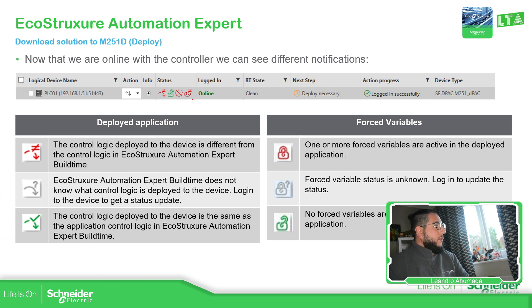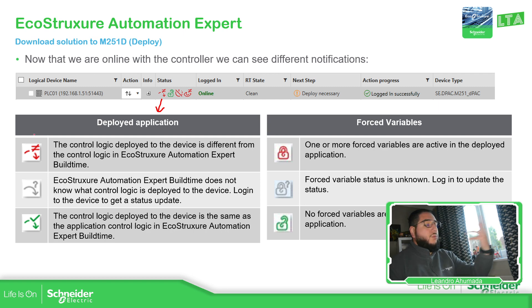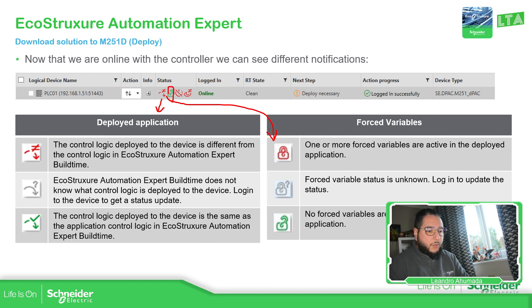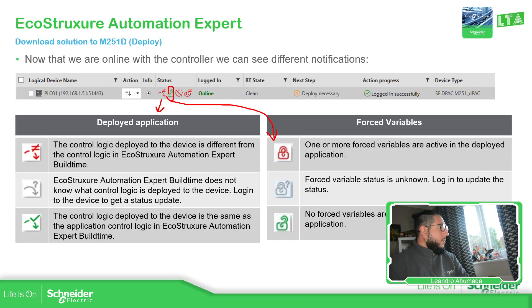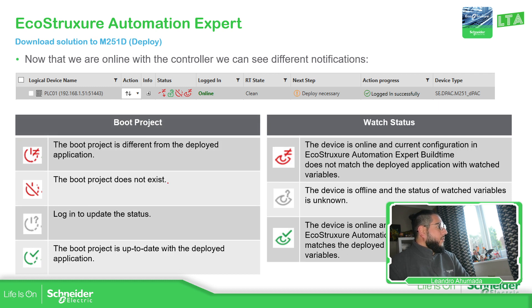As soon as you log in you have different things. This icon over here is about the application — basically it means the application you have on the software is different from what's on the controller. That's why we need to deploy. This lock icon is related to force variables. This one over here is related to the boot project — I have a different application installed there with a different boot project, which doesn't match the actual project I have in the software.